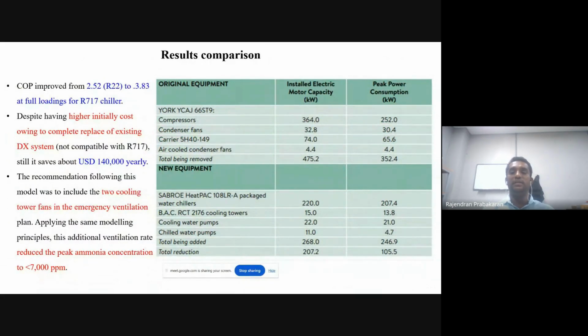So with this study, they introduced an additional ventilation fan in the chiller room. This helped to reduce the ammonia concentration within the room to less than 7,000 ppm, because ammonia is highly toxic. So it is not recommended for a person to stay when it is leaking. The installed capacity is about 252 kW of compressor, and they used two kinds of system. One is an air cooled system and the other is a water cooled system.